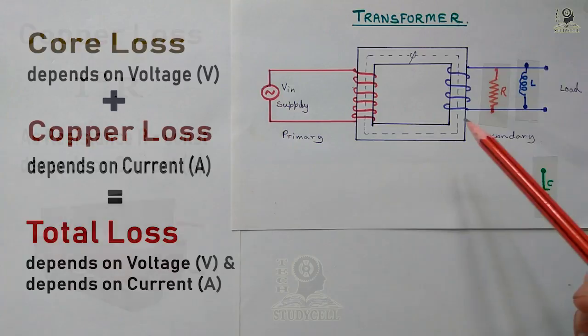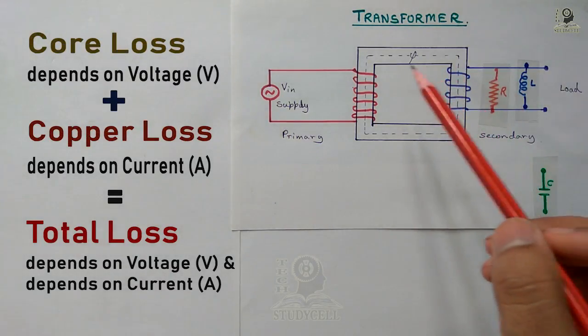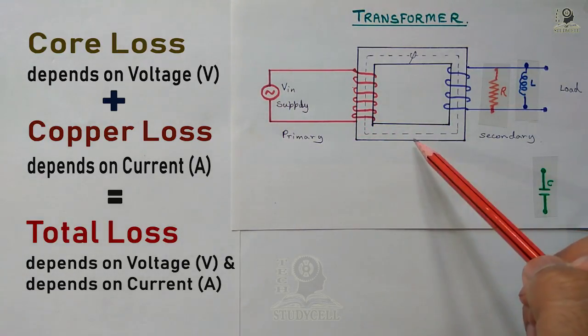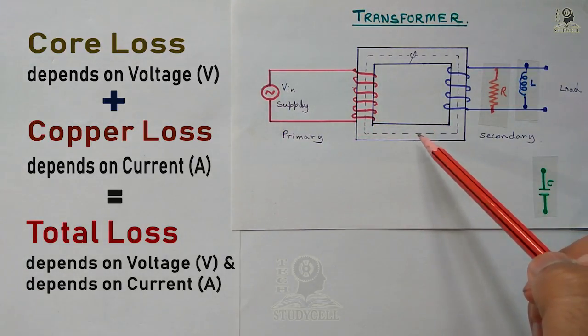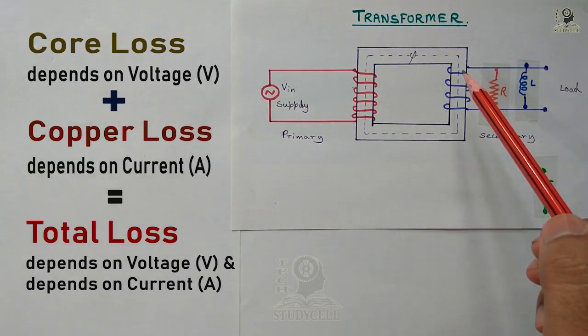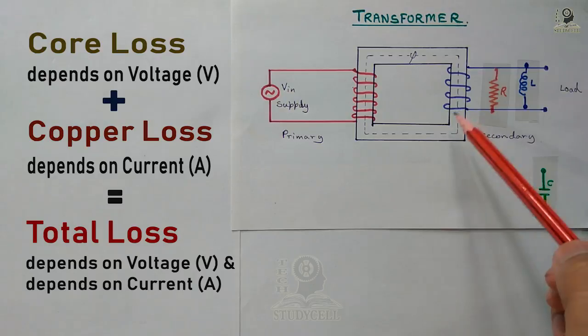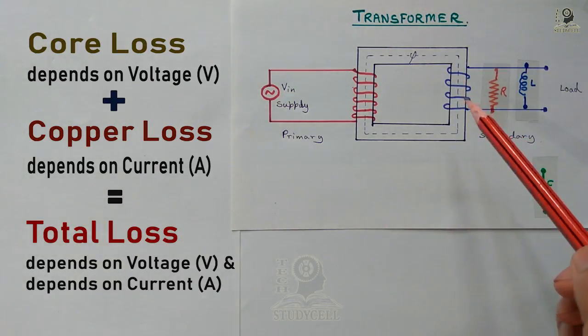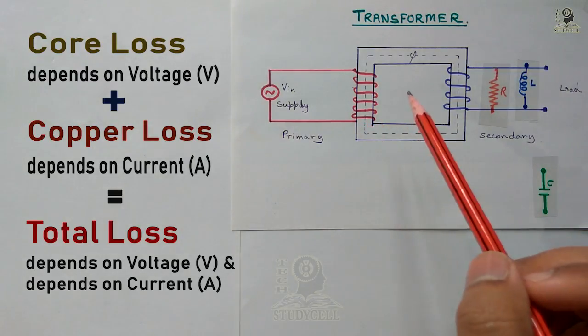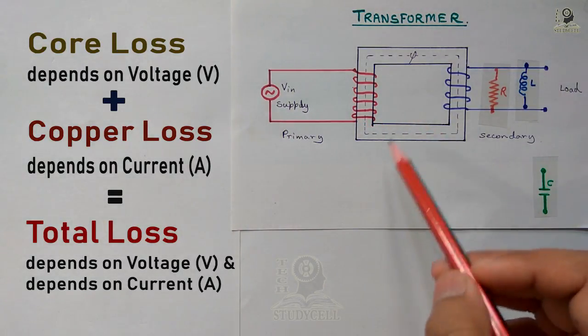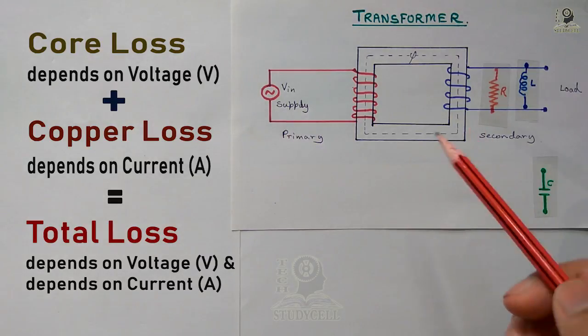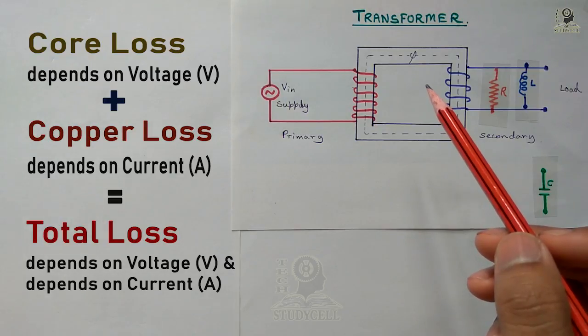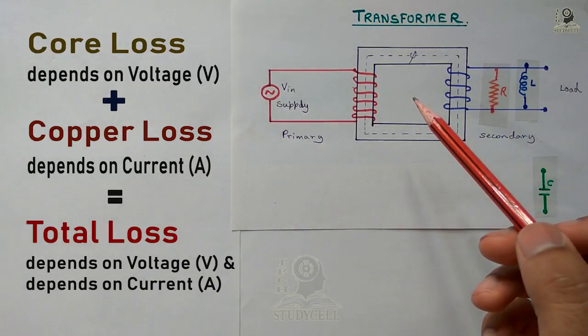So we have seen two types of losses: core loss and copper loss. Core loss depends on the voltage of the transformer, as the magnetic property of the transformer core is constant. Copper loss depends on the current flowing through the winding, as the resistance (R in I²R) is constant for a winding. Therefore, the losses in the transformer depend on both voltage and current only. So we rate the transformer in VA, or kVA, or MVA if the rating is higher.